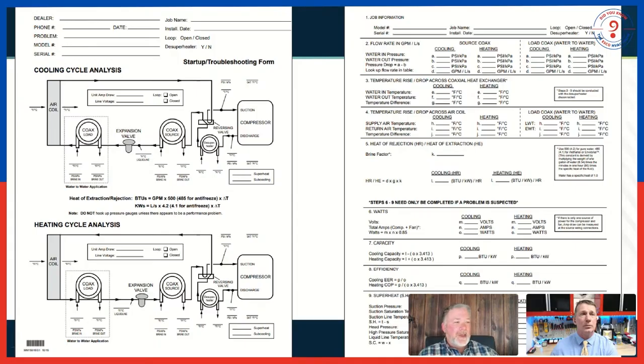The nice thing about that is we realize, as geothermal trainers, not everybody does geothermal every day. I'll get people call up and say, hey, I'm trying to do subcooling, where's my liquid line? I'm like, well, where's your liquid line on a conventional system? And they're like, well, gosh, I think it's after the condenser. I'm like, well, exactly—same thing. It's after the condenser. Liquid line is always after the condenser because that's where the liquid's at. So we try to make it easy there.